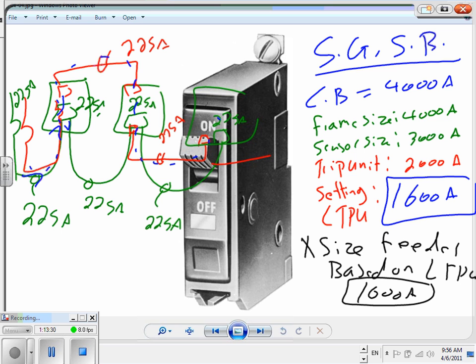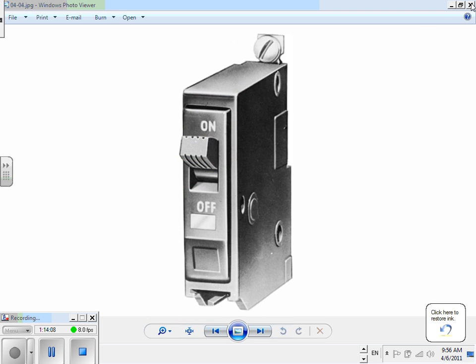Electronic circuit breakers make a lot of sense, guys, at 1,000 amp and higher, because you can tweak them. I can tweak a 1,000 amp electronic circuit breaker to pick up 50 amps with sensors and plug-in. I can make a 1,000 amp circuit breaker pick up 100 or 50 amps by changing the trip and the sensing, all the way down to 50 amps. Or even 55 amps, by the way. There's no 55 amp circuit breaker, you know what I mean? I can make a 55 amp circuit breaker through the settings. Okay, any question, guys? Any question about that? So that's what I wanted to mention about these.